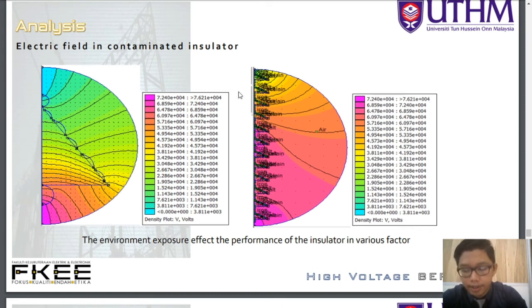In contaminated insulator, the insulator will be affected by contaminants from the environment, air, and salt, which affect the insulator performance and weaken the electrical field condition. The most common are insulation degradation, transmission lines, and substation insulators exposed to contaminants in the air, gradually getting coated with salt. The contamination arises mainly from industrial emission, so these affect the insulator performance. As you can see, the electrical field becomes weak for these two insulators.